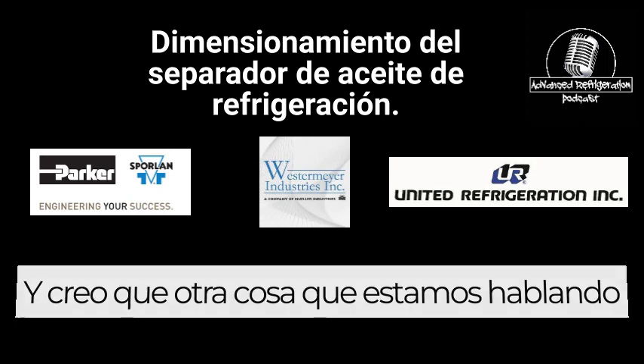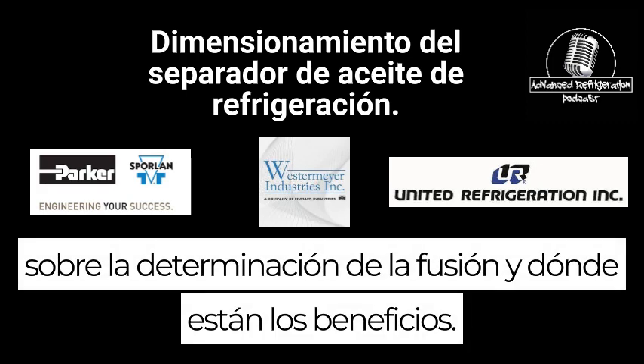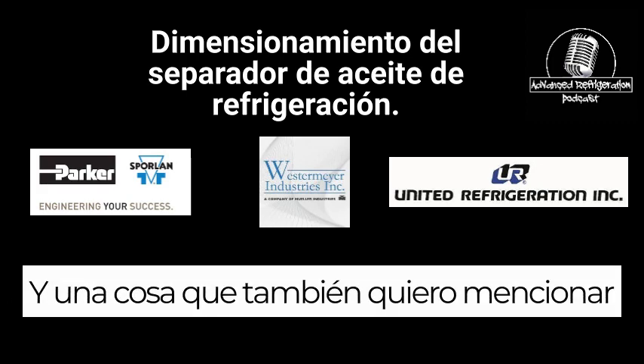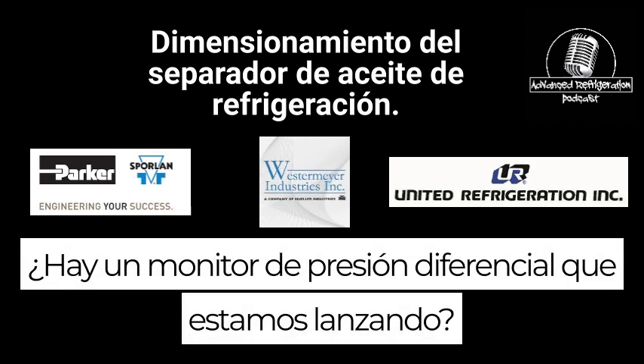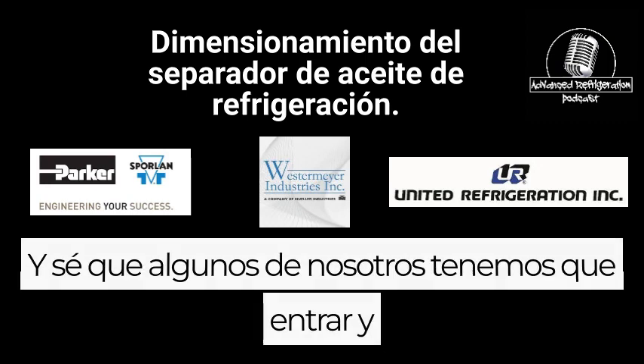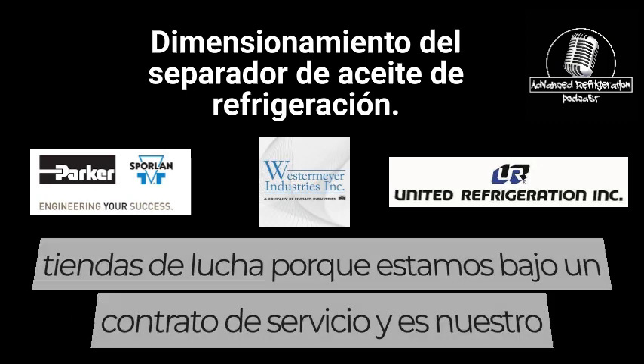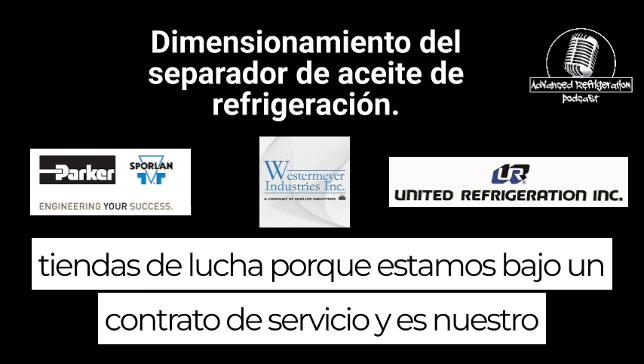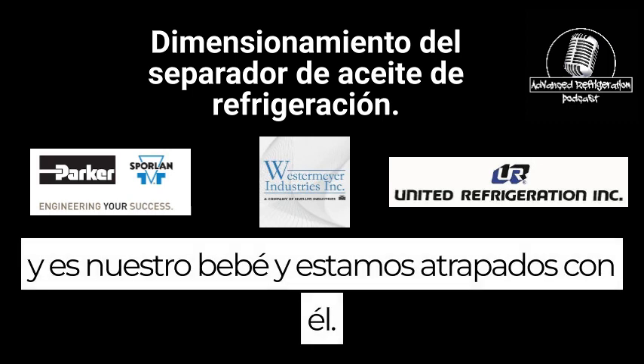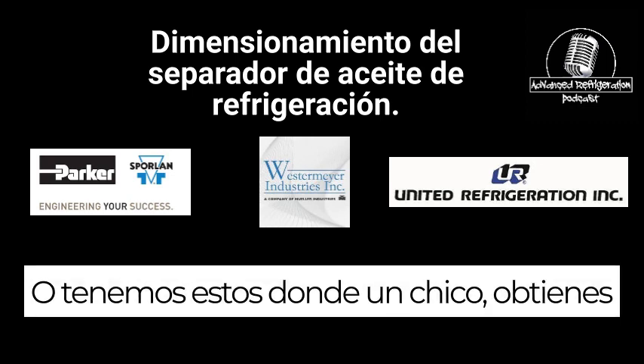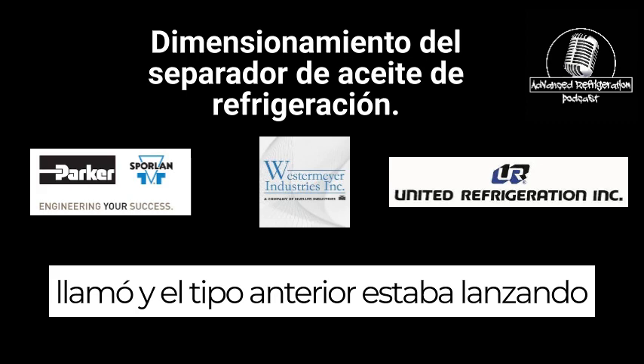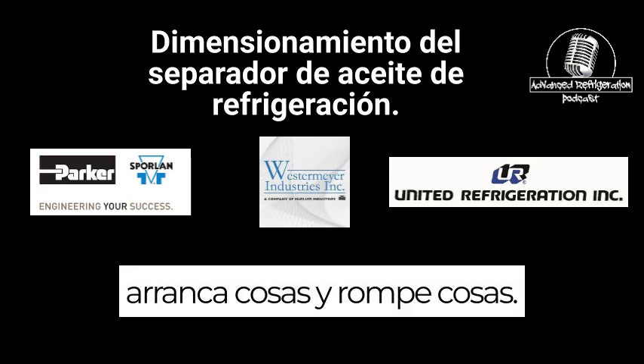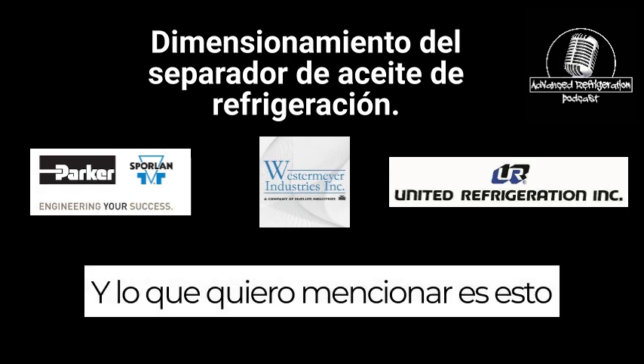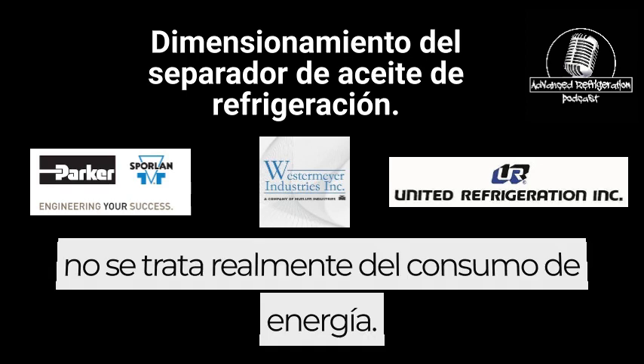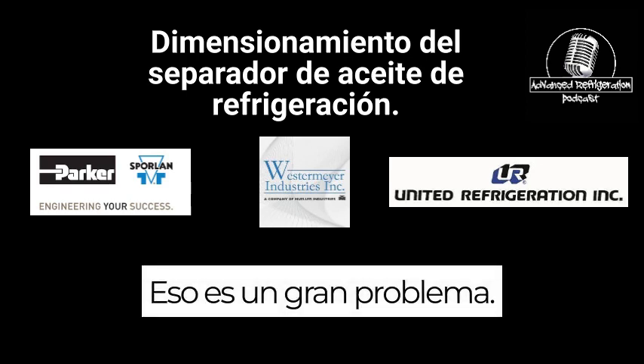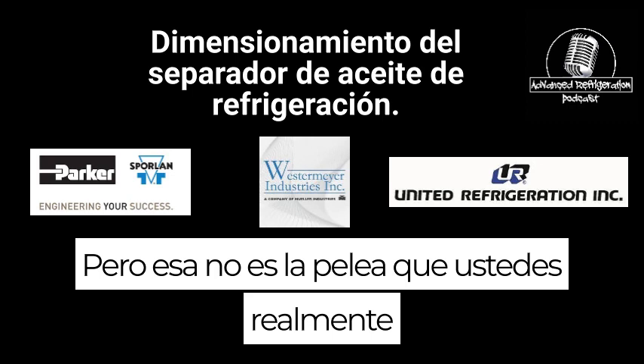Right. And another thing, talking about determining coalescing and where the benefits are, is a differential pressure monitor that we're launching. I know some of us have to go in and fight stores because we're under a service contract and it's ours and it's our baby and we're stuck with it. Or you get called in and the previous guy was just throwing wrenches at stuff and breaking things off. What I want to mention is the benefit of monitoring pressure drop, and it's not really about energy consumption. That's a big deal, but that's not the fight that you guys really have to carry.